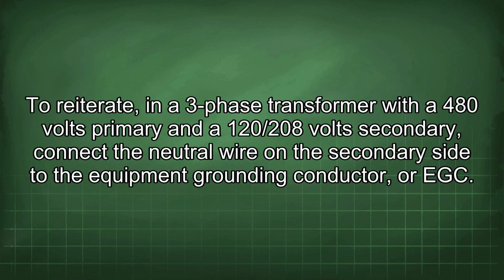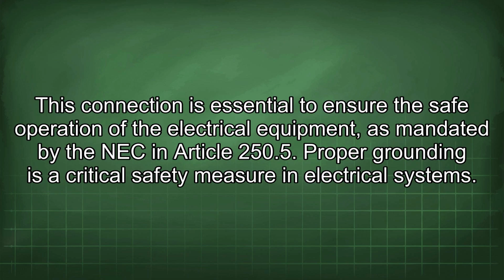To reiterate, in a three-phase transformer with a 480 volts primary and a 120/208 volts secondary, connect the neutral wire on the secondary side to the equipment grounding conductor, or EGC. This connection is essential to ensure the safe operation of the electrical equipment, as mandated by the NEC in Article 250.5. Proper grounding is a critical safety measure in electrical systems.